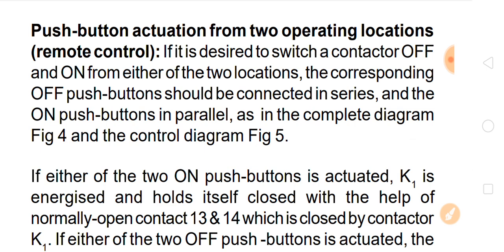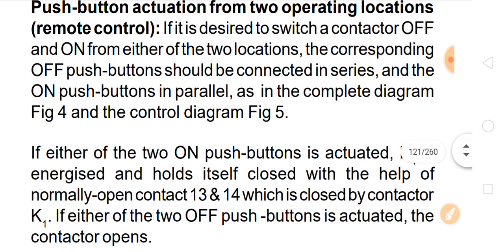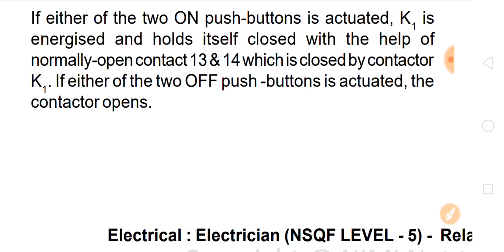Push button actuation from two operating locations — remote control: if it is desired to switch a contactor off and on from either of two locations, the corresponding off push buttons should be connected in series and the on push buttons in parallel, as shown in the complete diagram picture four and the control diagram. If either of the two on push buttons is actuated, K1 is energized and holds itself closed with the help of the normally open contact.